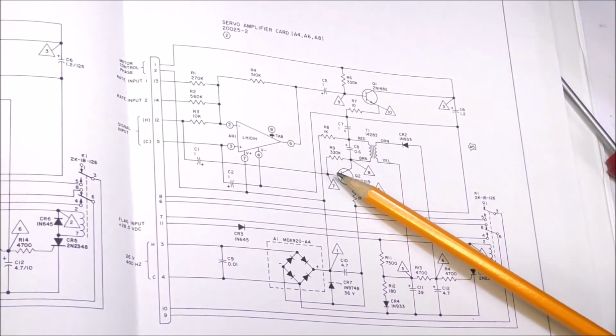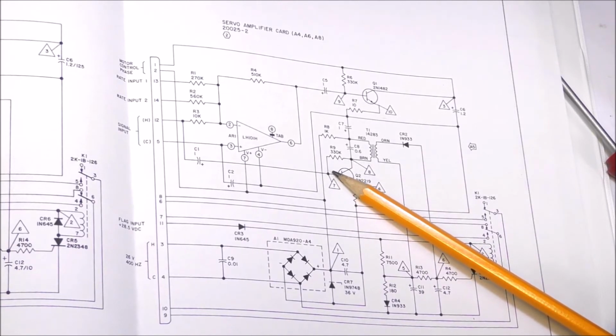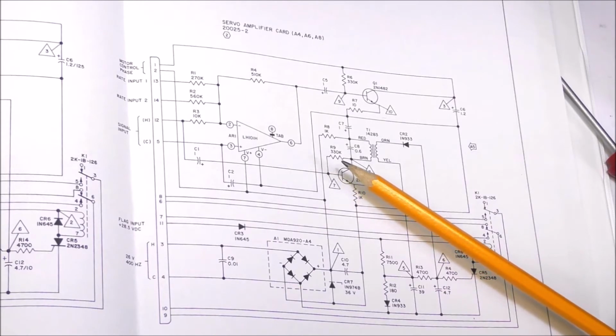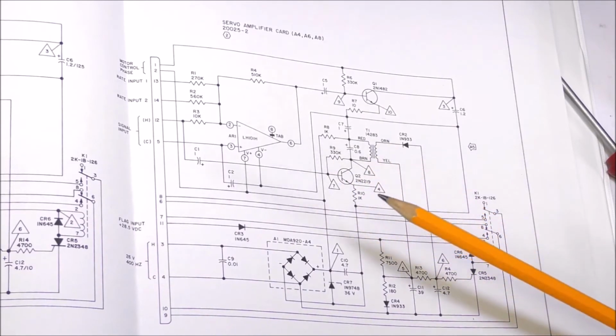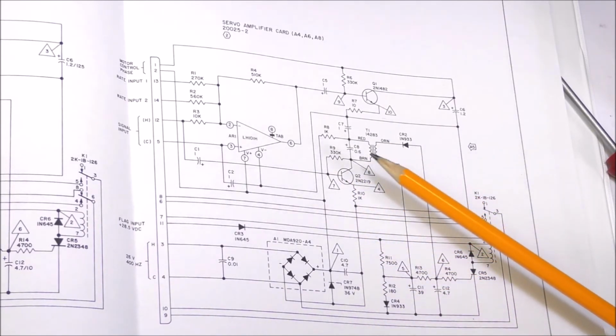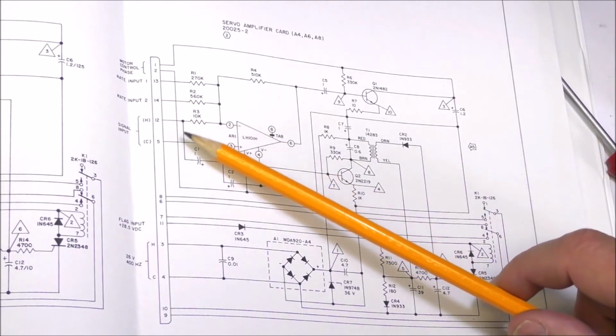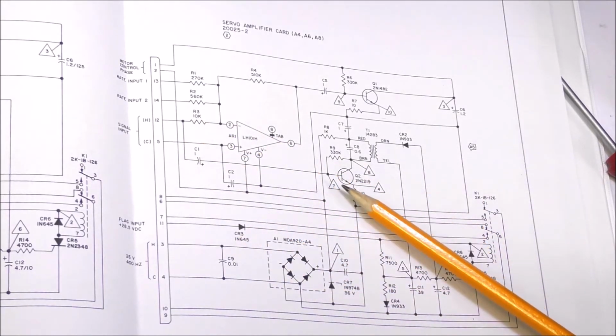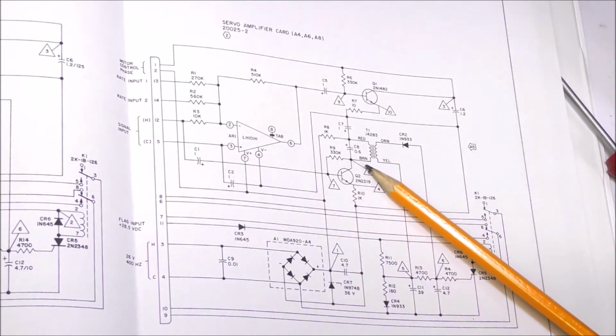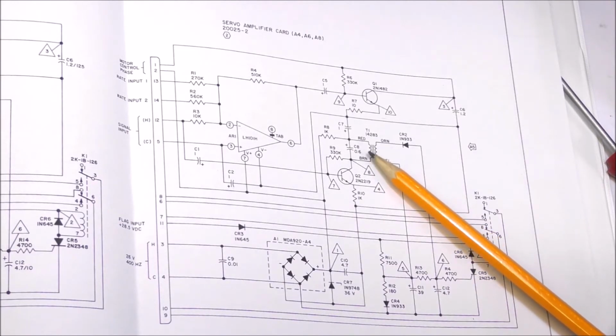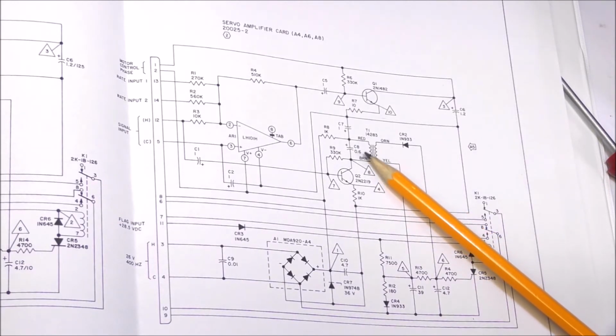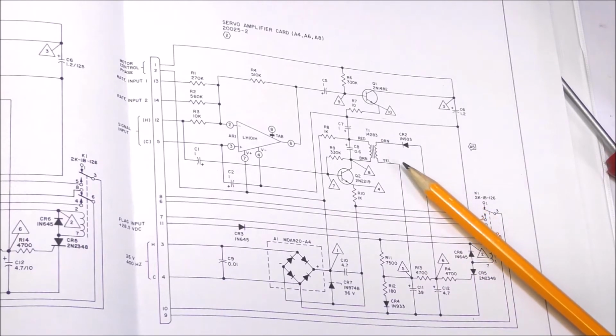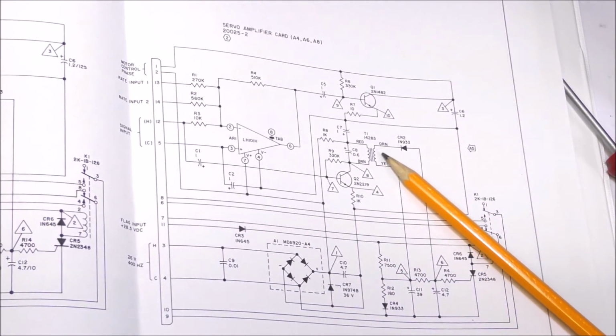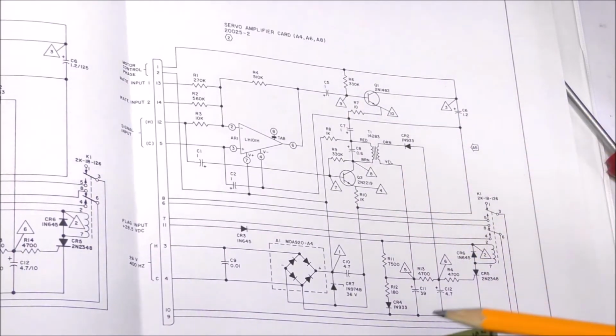This permits to know if the pick-off voltage is 0 or not, because normally when the loop is closed, when the servo control loop is stopped, there is 0 volt at the pick-off sensor. If it is not the case, there will be a voltage across the primary of this transformer. So this voltage appears at the secondary of this transformer. This transformer is this one.